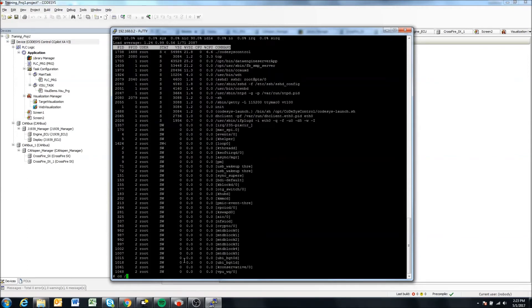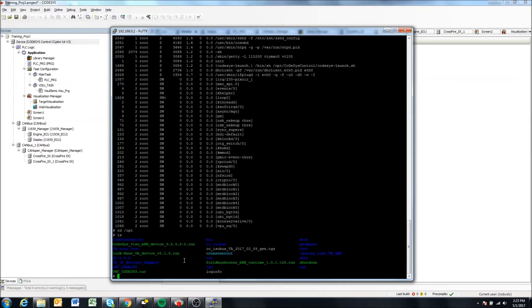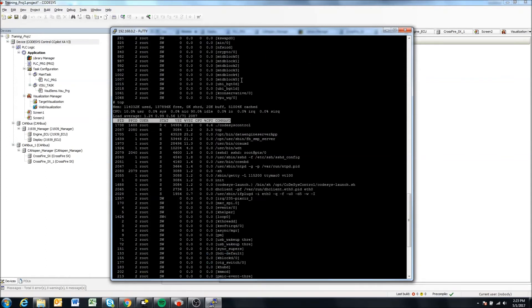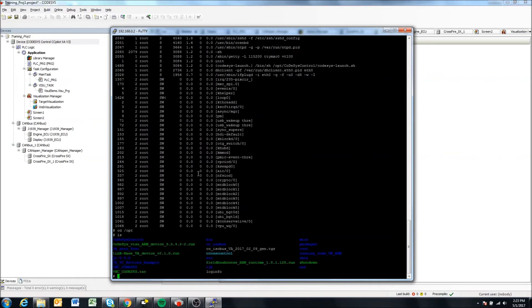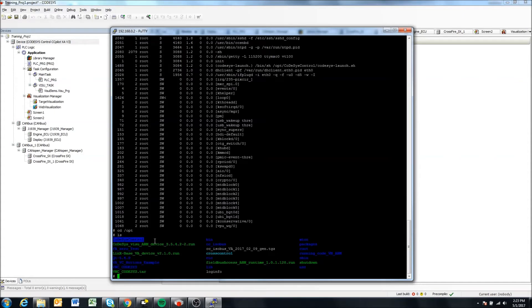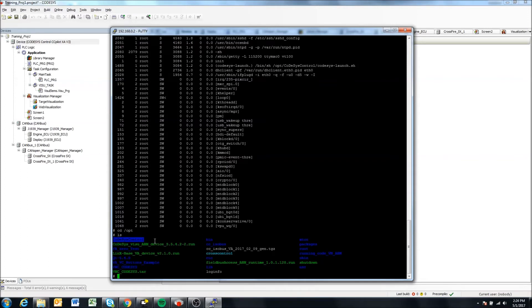Another check, we can go to the opt directory of the display with cd /opt and type LS. Displays with Codesys on them should have this Codesys control folder in that opt directory. If you don't see a Codesys control process running on your display and you don't have this folder, then you don't have Codesys installed. And that is your problem. Please contact Cross Control support to figure out why you don't have it installed if it was ordered with Codesys. Or if you made a mistake and did not order the display with Codesys, you'll have to contact Cross Control support and see how we can get that runtime onto the display.